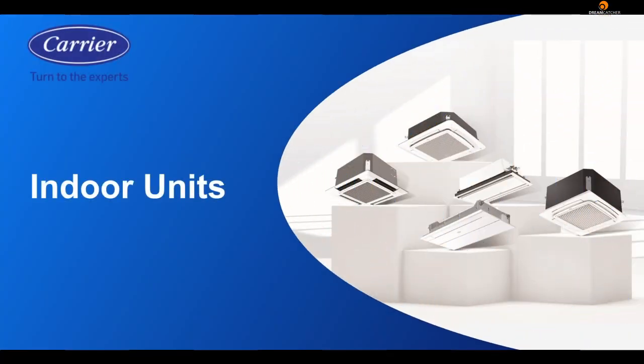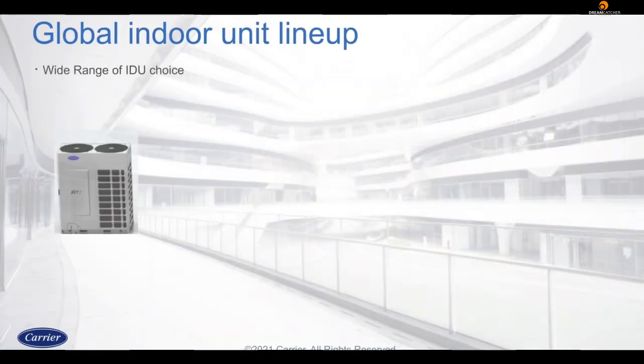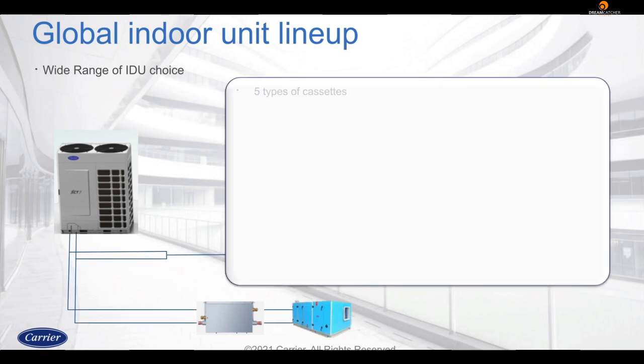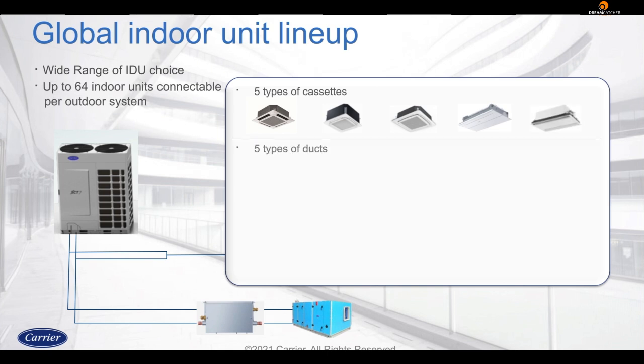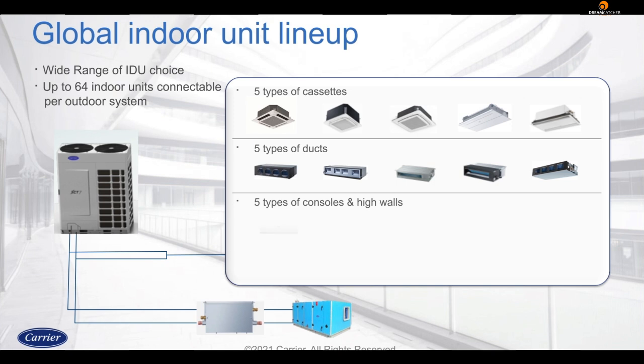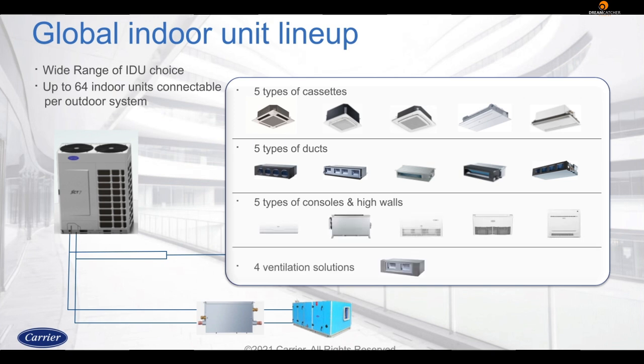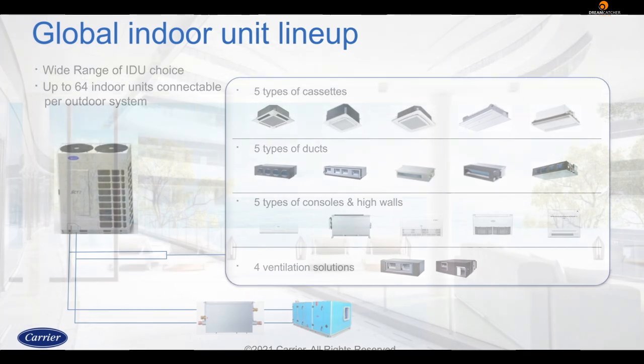Let us now look at the indoor units that come with the XET7 VRF system. The system comes with a wide range of indoor units that partner perfectly with the ODUs to provide you with the best air conditioning solutions. Up to 64 units can be connected per outdoor system. The IDUs come in a range of 5 types of cassettes, 5 types of ducts, 5 types of consoles, and high walls, along with 4 ventilation solutions.